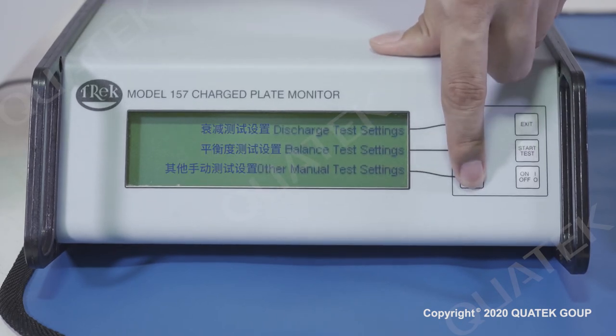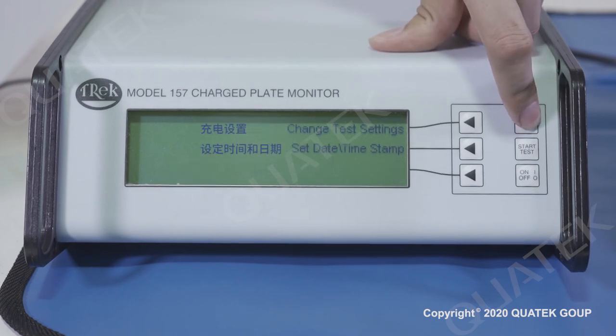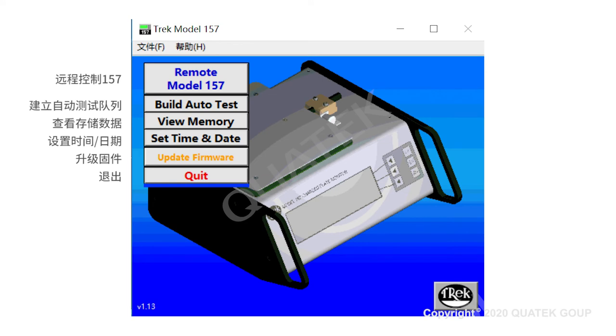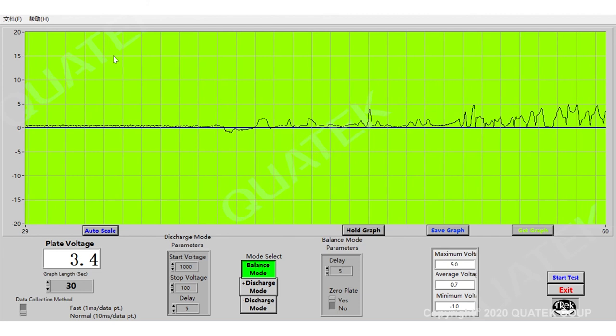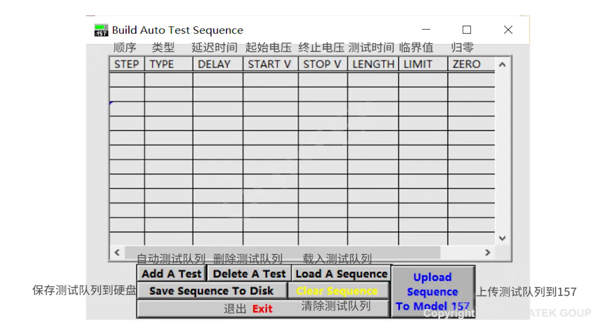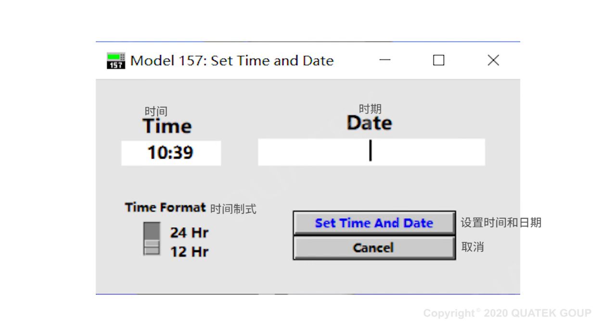We can also set the instrument to record manual data when manual measurement is performed. Lastly, we will introduce the software of TREK 157. The software can be run by connecting to a computer using the USB port. Selecting remote control for TREK 157 allows us to control the instrument and perform test measurements from the computer. The build auto test feature lets users design their own measurement sequence and upload it into the TREK 157 main unit. For viewing test results, users can view all saved measurement results and export them into Excel format by selecting save data. Users can also change the TREK 157 time and date as required.